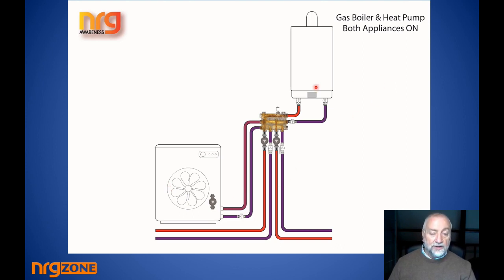In other words, from what we've just seen, you can have the heat pump on its own, you can have the gas boiler on its own, and you can have the two of them working in perfect unison to deliver, where you're preheating to a final output temperature that you decide based on your temperature, your pipe sizing, your pump sizing.